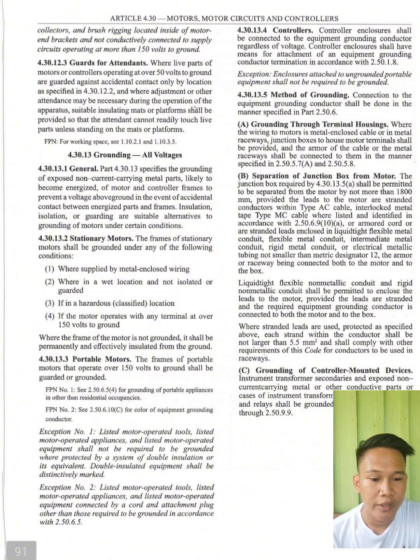Next, we have 4.30.13.4 Controllers. Controller enclosures shall be connected to the equipment grounding conductor regardless of voltage. Controller enclosures shall have means of attachment of an equipment grounding conductor termination in accordance with 2.50.1.8. There is an exemption: enclosures attached to ungrounded portable equipment shall not be required to be grounded. Next, we have 4.30.13.5 Method of grounding. Connection to the equipment grounding conductor shall be done in the manner specified in Part 2.50.6. So, you have grounding through terminal housings.